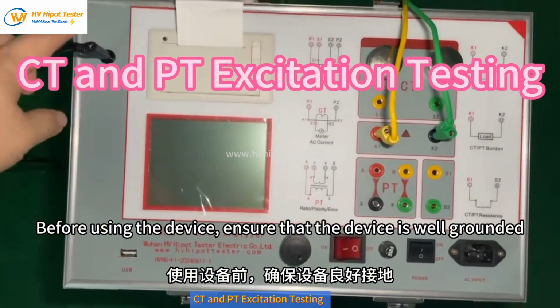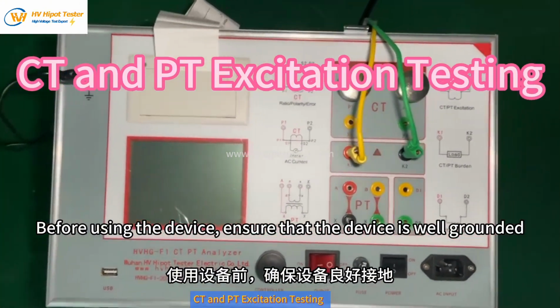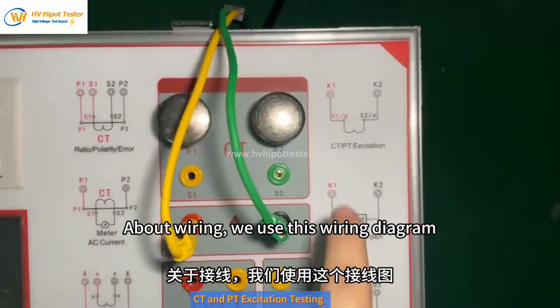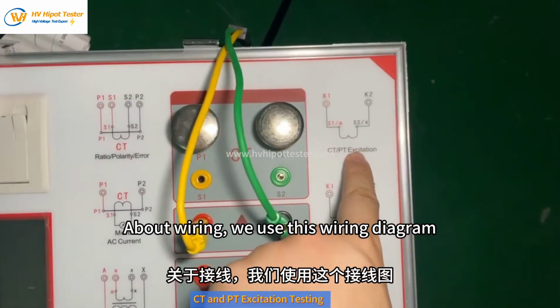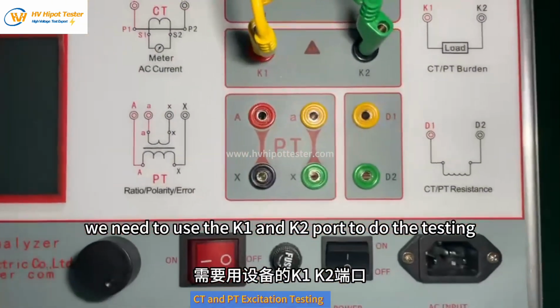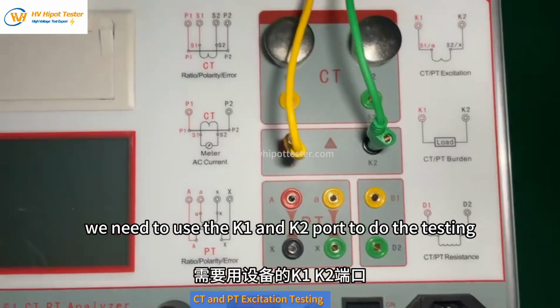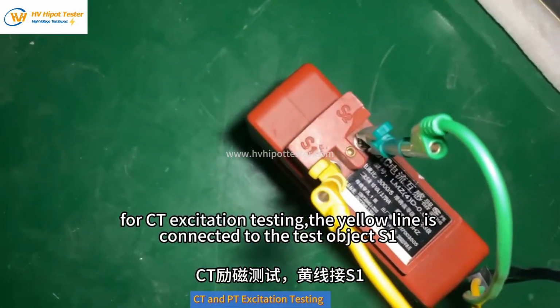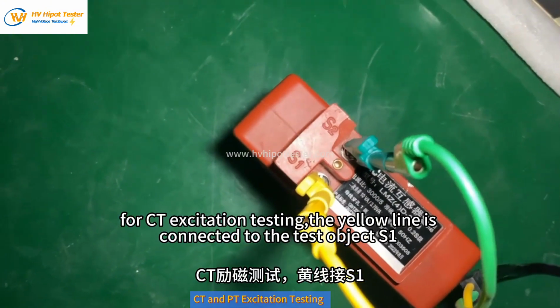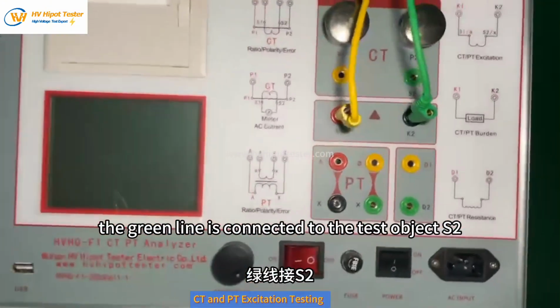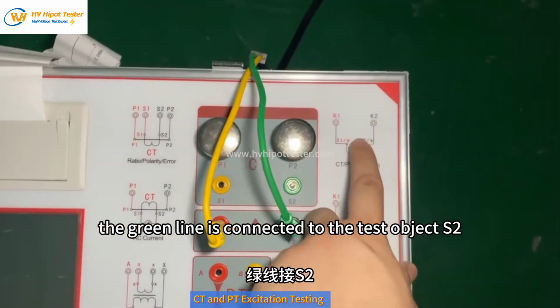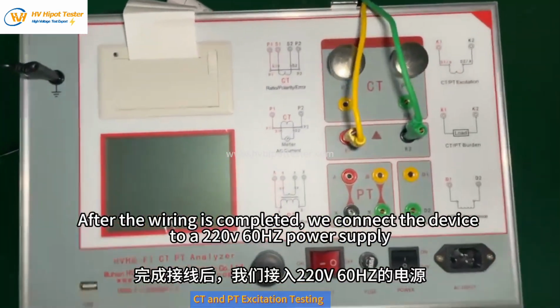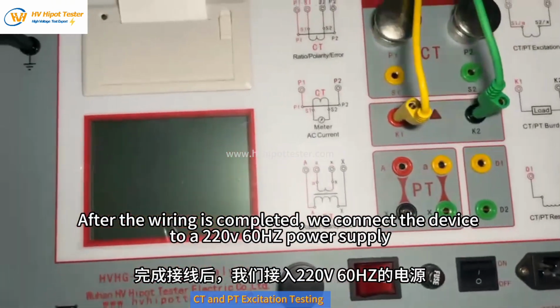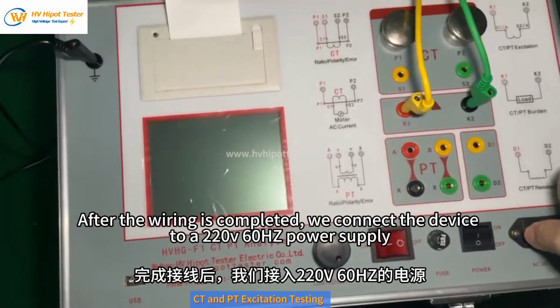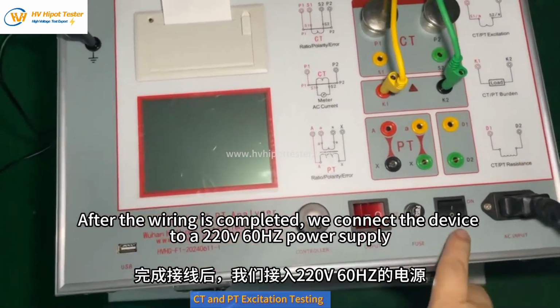Before using the device, ensure that the device is well grounded. About wiring, we use this wiring diagram. We need to use the K1 and K2 ports to do the testing. For CT excitation testing, the yellow line is connected to the test object S1. The green line is connected to the test object S2. After the wiring is completed, we connect the device to a 220 volts and 60 Hz power supply.